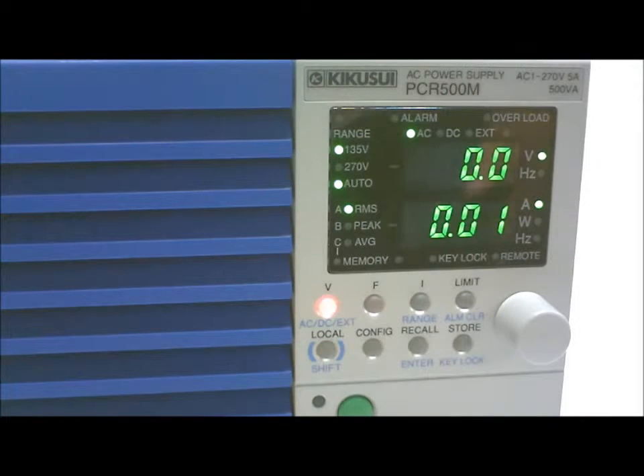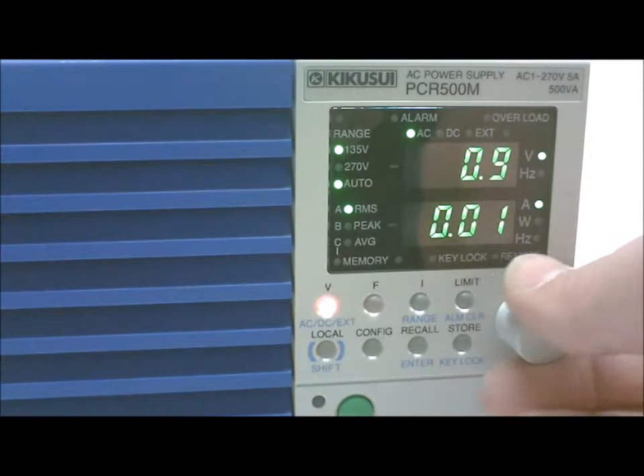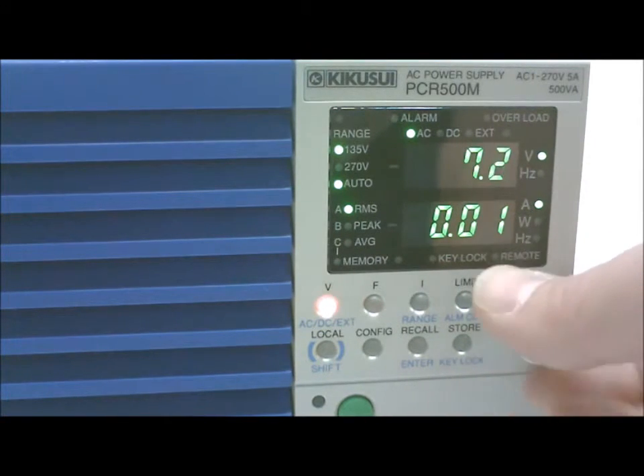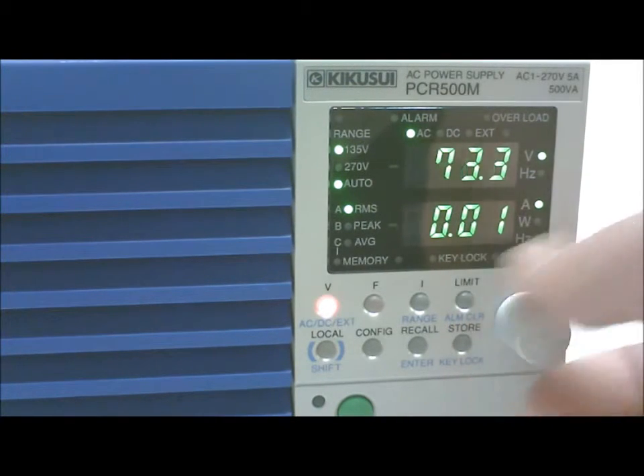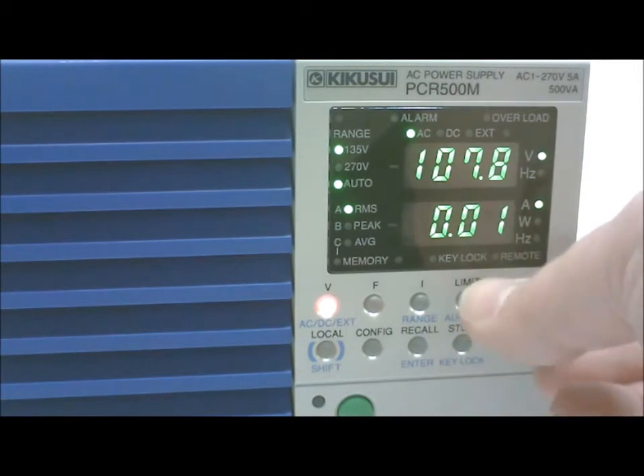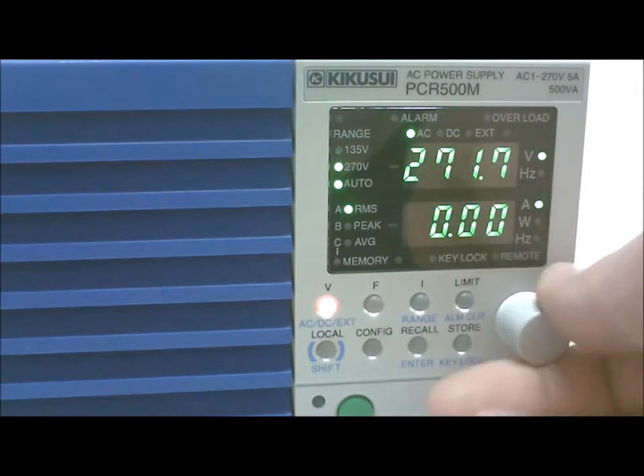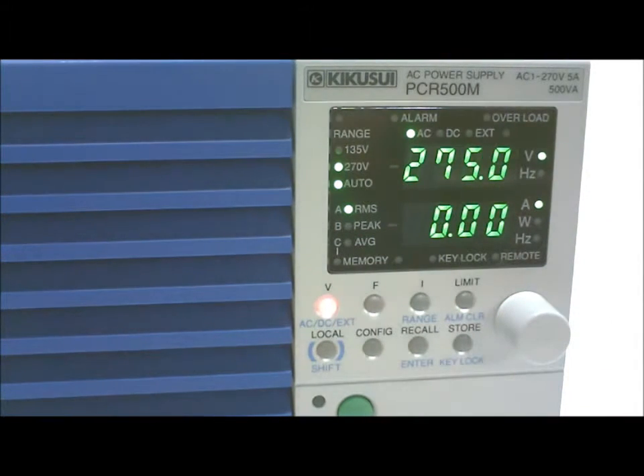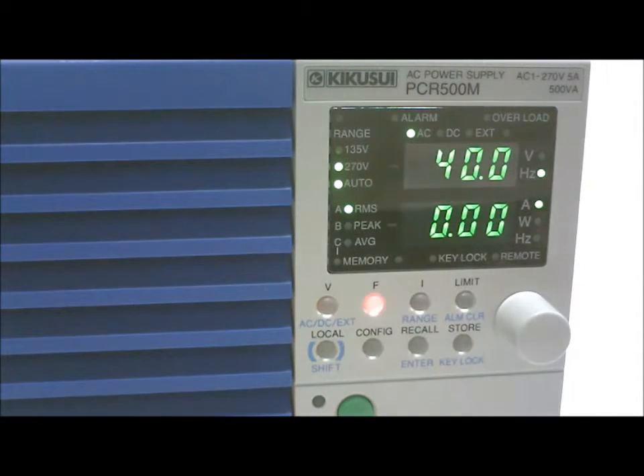The AC output voltage has very low harmonic distortion and is highly stable. It can be set between 1V and 270V. The frequency can be set between 40 and 500Hz.